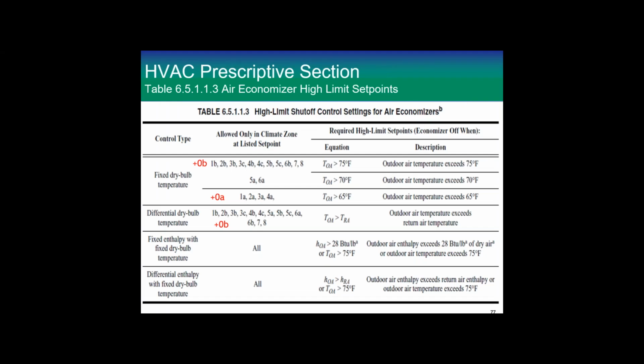So this is the way you control the economizer. You have different choices. Fixed dry bulb temperature is one way to control it. If you're doing that, then for the climate zones, this long list of climate zones, you have to hold it in economizer until your outdoor air temperature is above 75 degrees, which is hotter than you would think. But remember, we use a compressor assisted economizer. So at a certain point, as long as we're putting the outside air first, we let the compressor come on to help us. But you're holding that damper 100% open, and you're using it with the economizer.